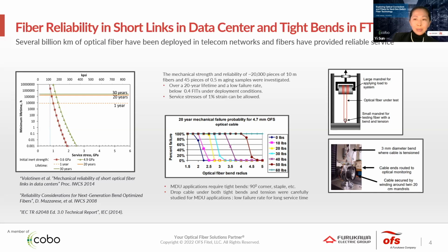And moving to the data center, the fiber can experience service stress higher than that. For example, fiber in the vertical direction in structured cabling, several meters, experiences some self-weight, but there are outstanding studies on this stress load issue. I quote a study back in 2014 at IWCS, and in that study, about 20,000 pieces of 10 meter fibers spanning 2 years of qualification tests and 45 pieces of 0.5 meter fiber aging samples were investigated for mechanical strength and reliability.